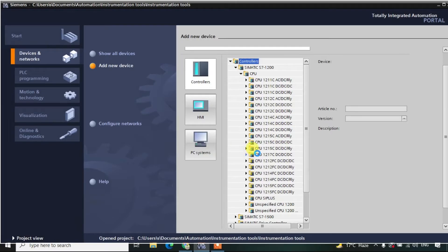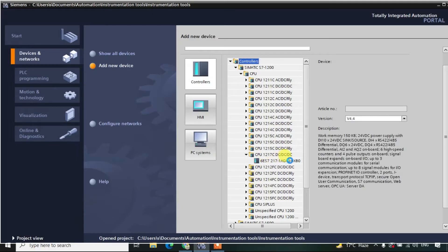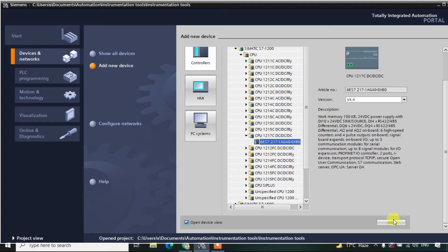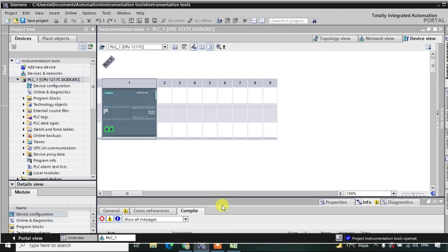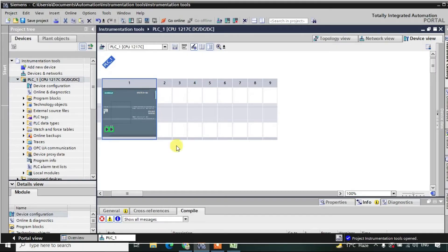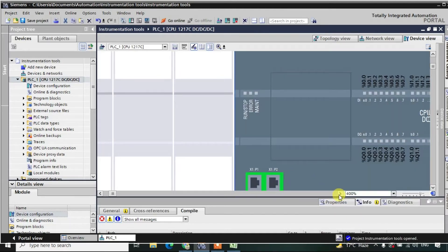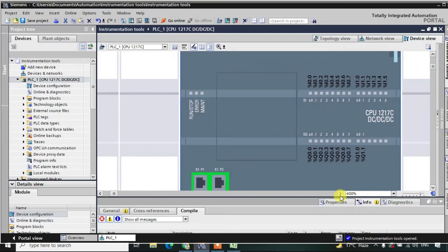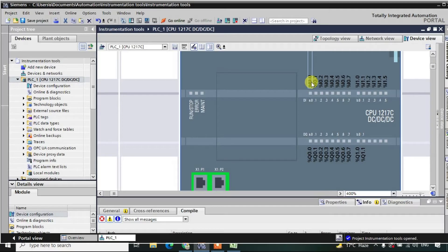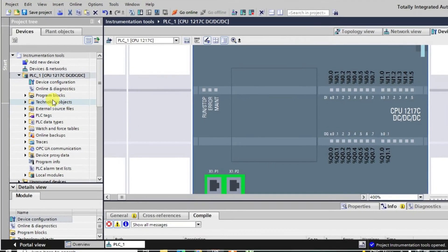Here we will be taking CPU 1217C DC/DC/DC. One important thing to notice is that the version should be greater than 4.0, otherwise we can't work on the simulator — I mentioned this in the previous lectures as well. Now you can see the CPU is added, and if we maximize it we can see the number of IOs: digital inputs starting at address I0.0, I0.1, and so on, and digital outputs as well.